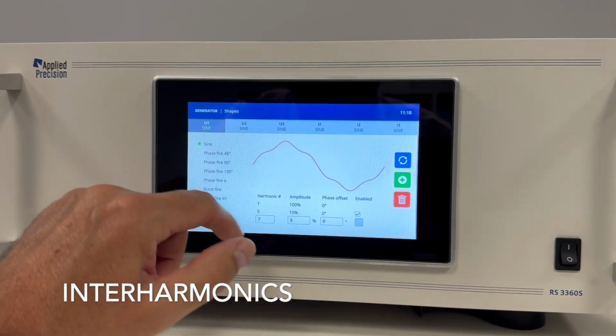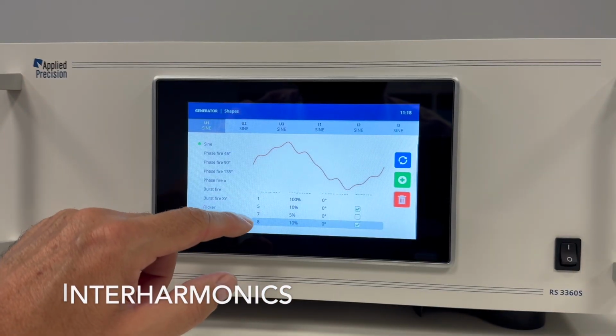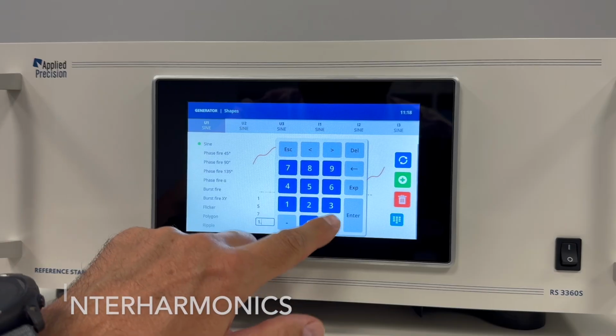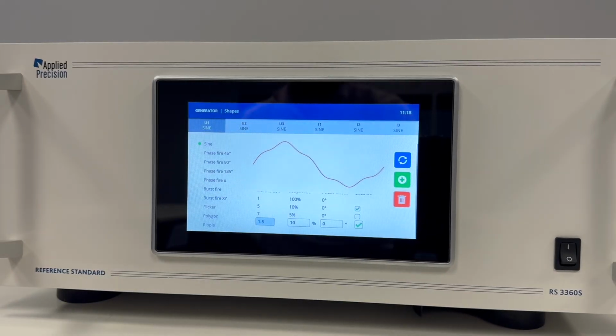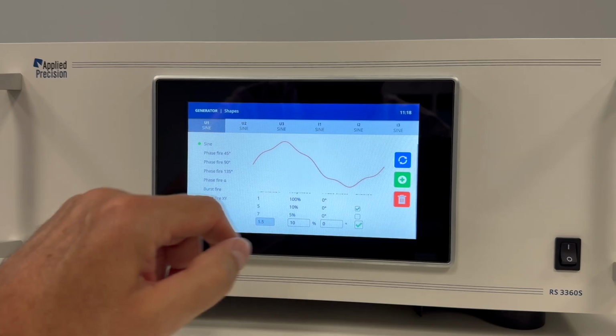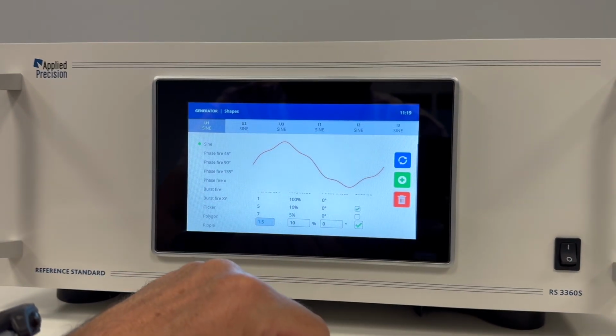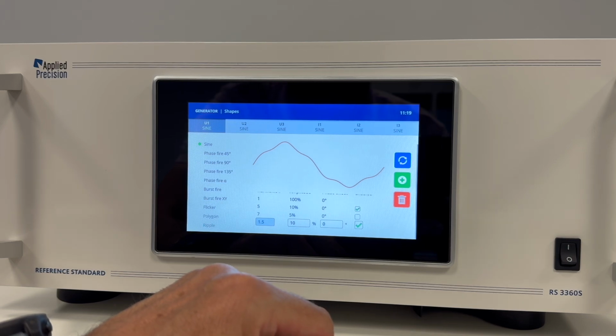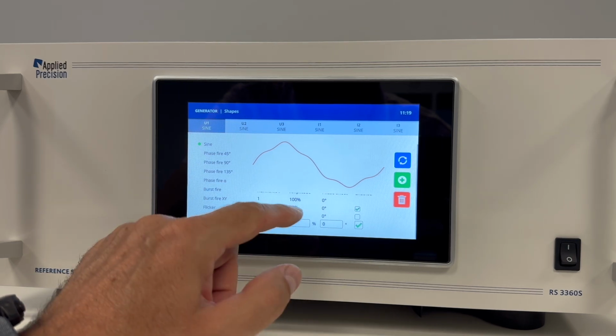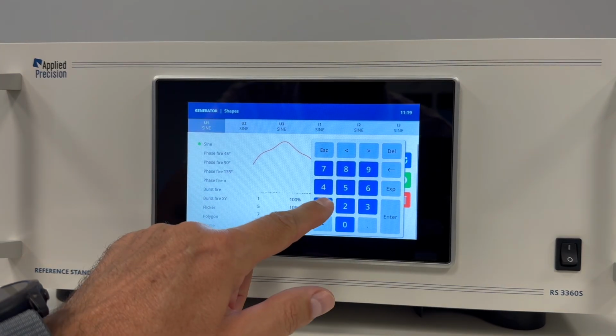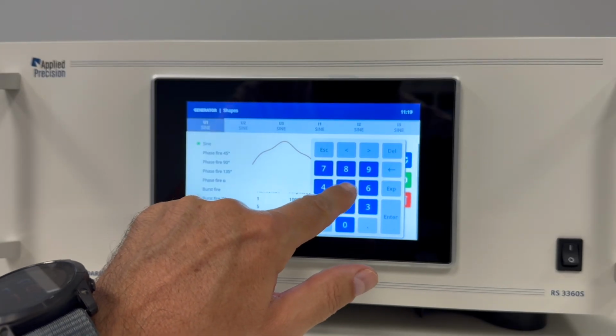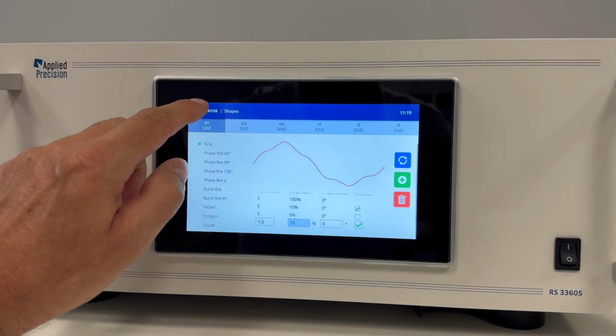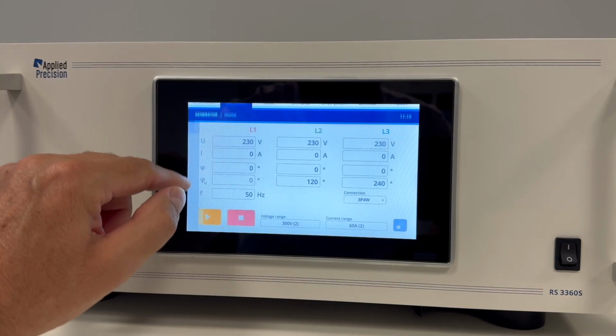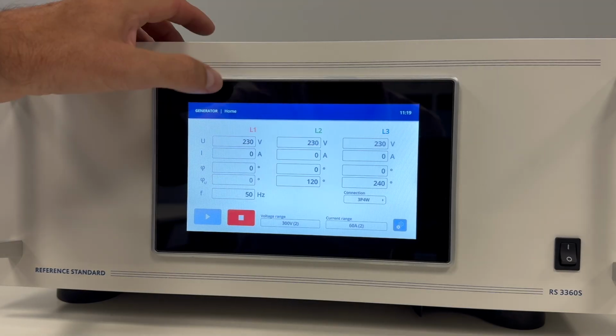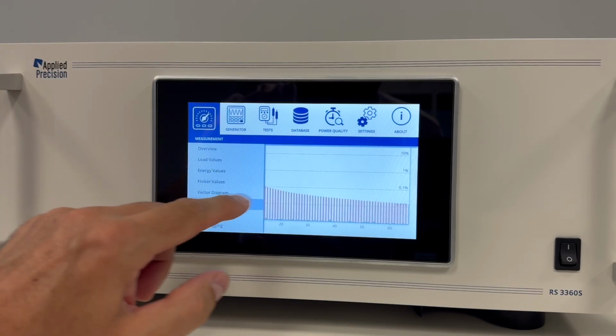Let's disable the seventh harmonic, and let's add, for example, the 1.5 harmonic. The signal is running at 75 hertz, because the fundamental is now 50 hertz, so the 1.5 harmonic will be 75 hertz here. So let's try to generate it. We can set it to 15%, for example. So let's switch again to the home screen. Okay, we're generating, and let's check the measurement part and the harmonics.